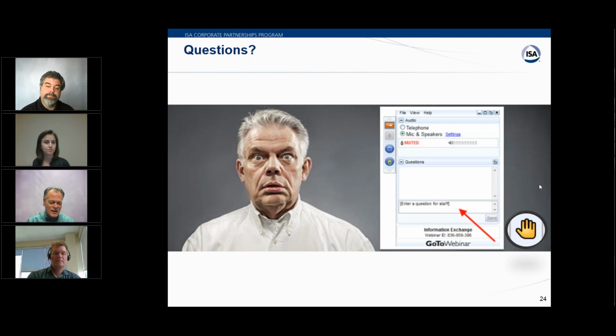As far as good practice goes, what time do you allow for a probe to settle? I think it's trial and error. Roy just made a good point. Roy, you had to do a little shuffle there for what, 60 seconds, no more than 2 minutes, and it moved from 4 to 10, and it stabilized at 9.9. So at least a minute. I was going to say roughly a couple of minutes is probably reasonable. In most cases you should get pretty close in 2 minutes. Some people say 5, but that's not a bad thing.